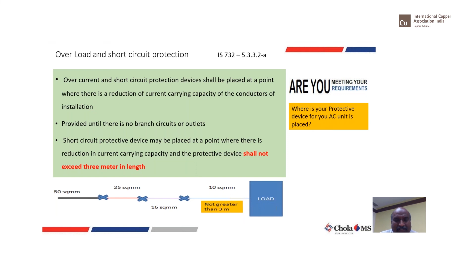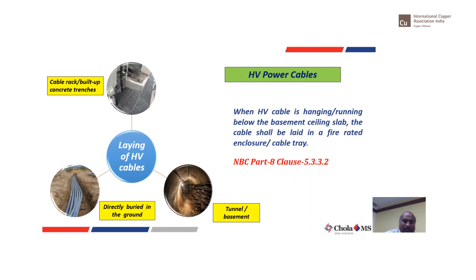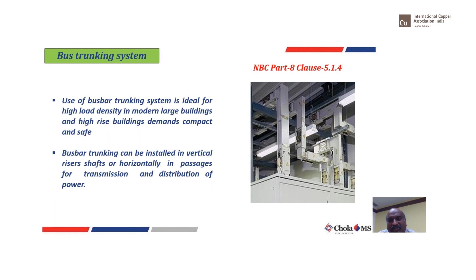Whenever you're laying cables, HV cables, of course, you all know you lay them in trenches, you bury them under the soil as underground cables, or you might have a tunnel, or you might have proper cable trays. So depending upon the way that you lay the cables, please consider the de-rating factors before taking it forward. Okay, there are certain improved ways. Bus trunkings are now catching up in most of the high-rise buildings. If you feel that cables are a problem, then copper bus bar trunkings are another way you can improve the overall power distribution and still ensure safety in high-rise buildings. So you can look at these types.